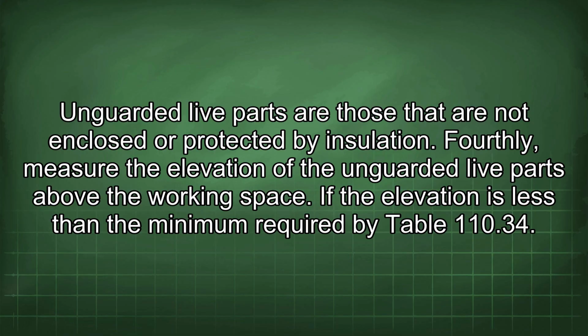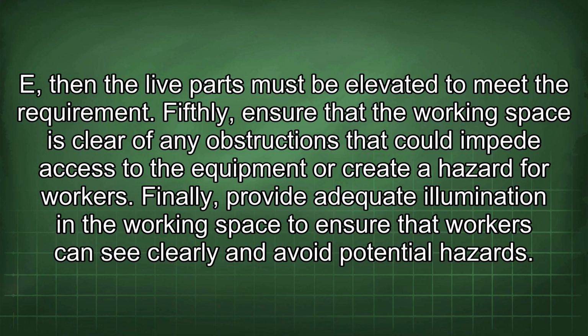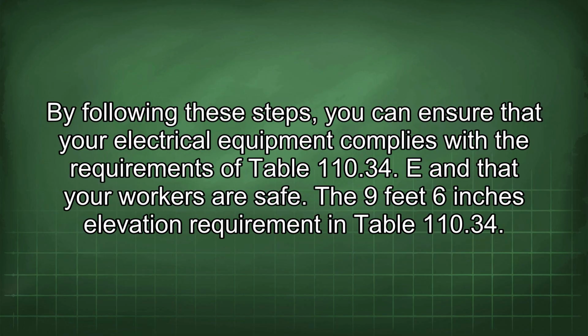If the elevation is less than the minimum required by Table 110.34, then the live parts must be elevated to meet the requirement. Fifthly, ensure that the working space is clear of any obstructions that could impede access to the equipment or create a hazard for workers. Finally, provide adequate illumination in the working space to ensure that workers can see clearly and avoid potential hazards. By following these steps, you can ensure that your electrical equipment complies with the requirements of Table 110.34 and that your workers are safe.